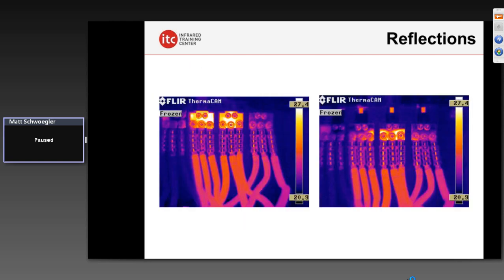Proper image adjustment is very important. We also get into the physics of heat transfer in our Level 1 training classes — specifically how infrared radiation behaves. We see some electrical connections here, and on the left what appears to be potentially a connection problem. What we learn in training, though, is that infrared radiation — just like visible light radiation — can reflect off of objects. You get up in the morning and look in the mirror and you're seeing a visible light reflection. Well, in the field, shiny unpainted metal surfaces reflect infrared radiation the same way. Those photons of energy will bounce off what we call a low-emissivity surface, and it's actually a reflection of the thermographer standing there opposite these connections. This can be very confusing, sometimes making it difficult to tell whether the hotspot you're looking at is legitimate or not.